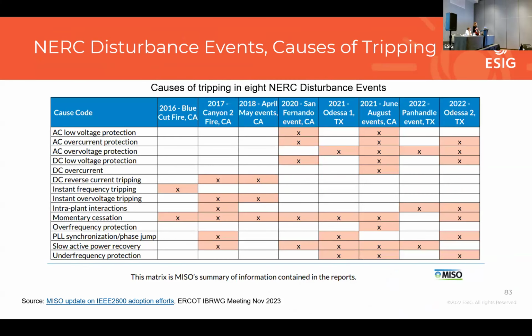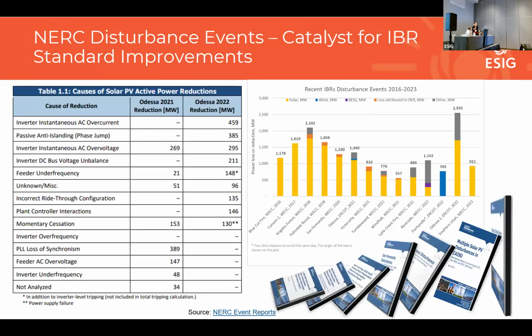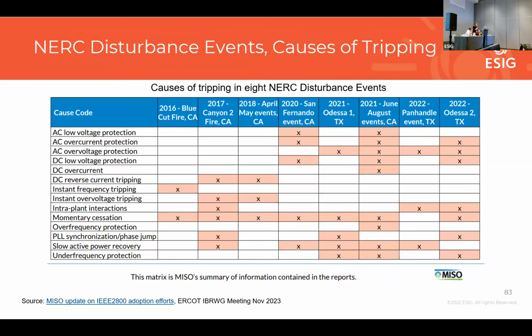So this is a chart from MISO that I quite like. I basically put all these events together on one plot, but they went one step further and looked at the causes of tripping of inverter-based resources in these events. And you can see that some of these causes are pretty common.